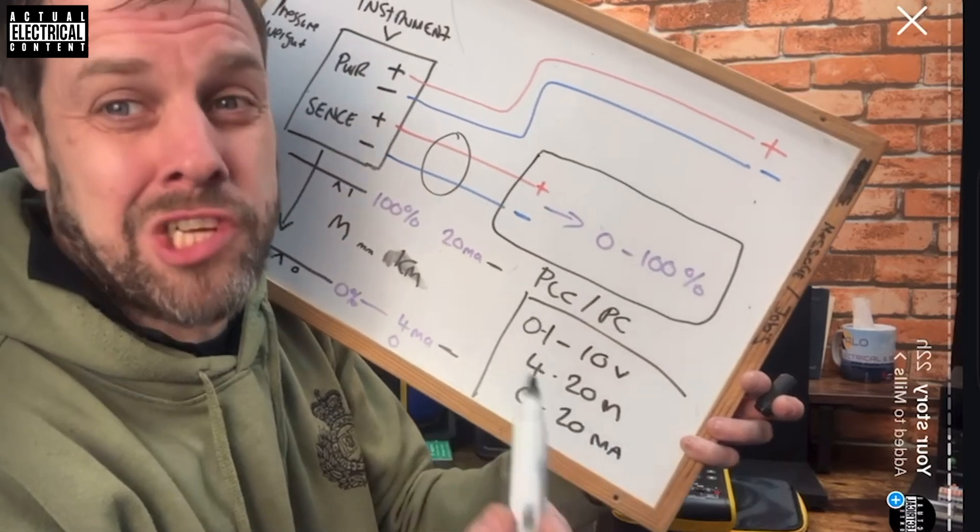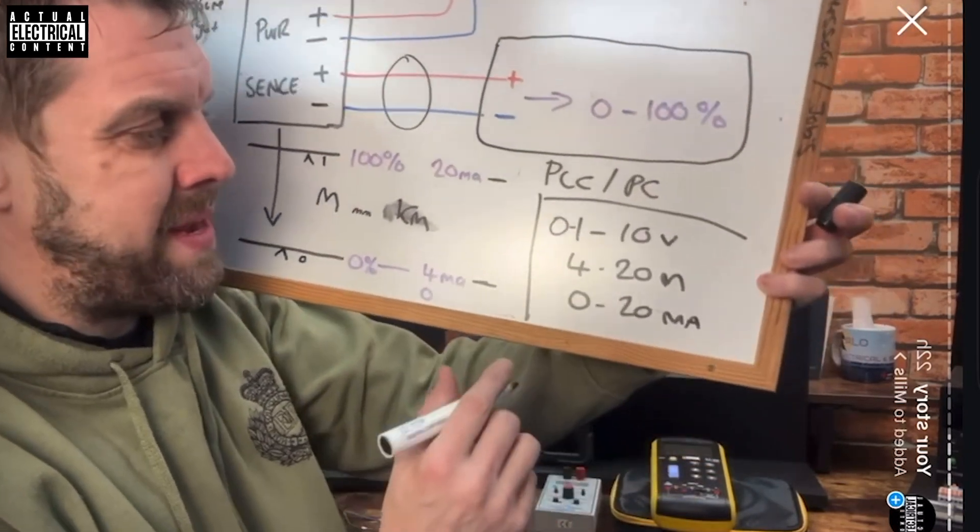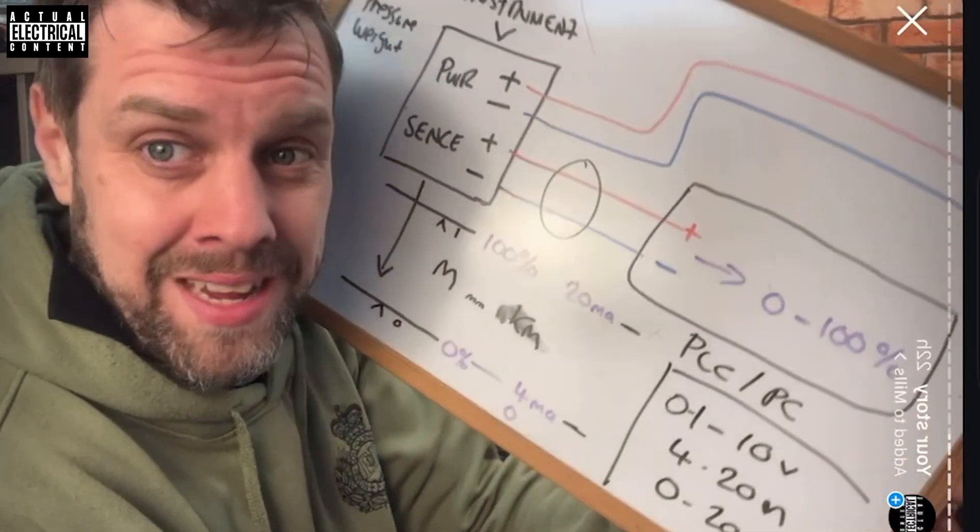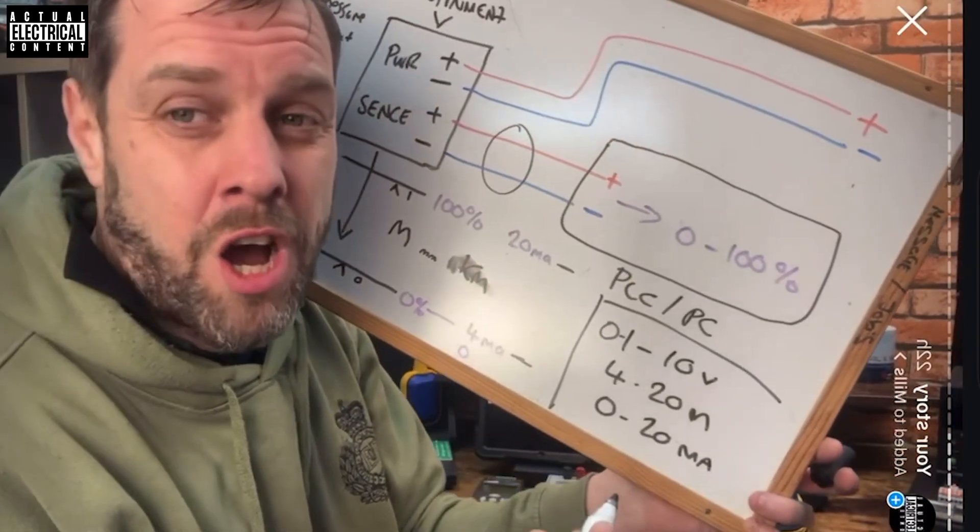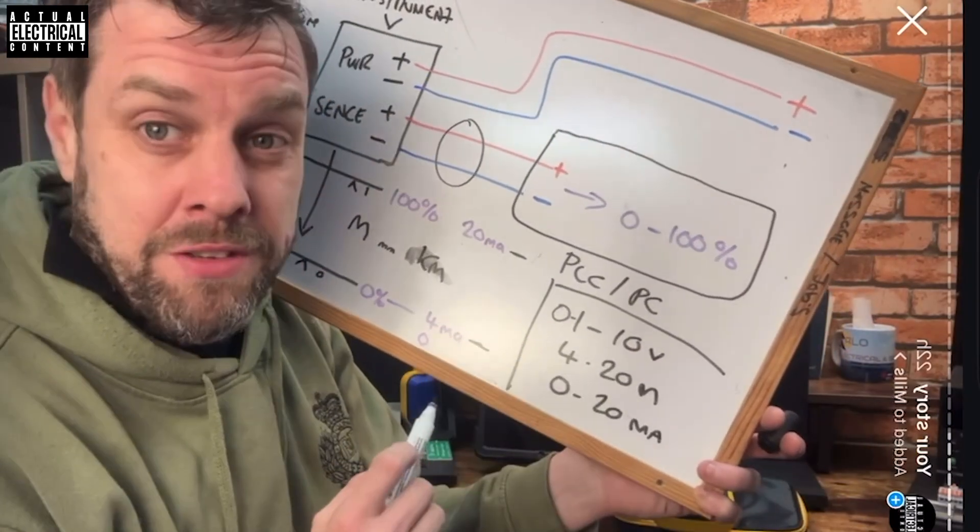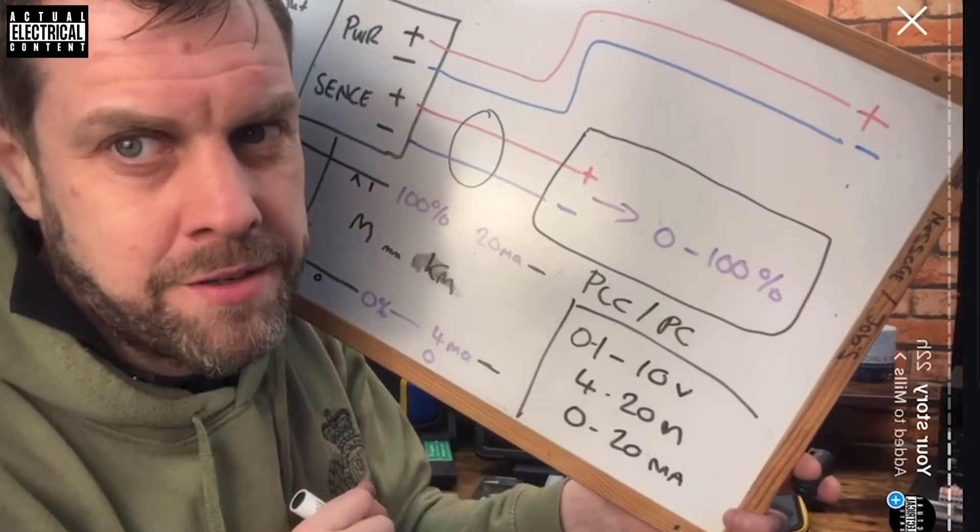The lowest milliamp available is four and the highest milliamp available is 20. Therefore, we assign zero percent to four milliamps and 100 percent to 20 milliamps. I'm going to talk about why that is, but just remember four is assigned to the lowest process value, 20 is assigned to the top process value, and that's the range that we're going to work in. But let me talk about outside that range.